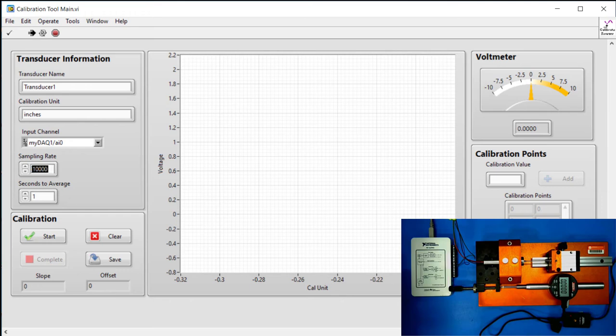Now you're going to select a sampling rate. If your system can sample 10,000 samples a second, and that's what you normally run, that's great. This system we're going to run at 1,000 samples a second, and you can select how many seconds you would like to average, 1, 2, up to however many. Generally, somewhere around 1 or 2 is just fine unless you have significant noise problems, in which case there may be some other things we can do to help your system.